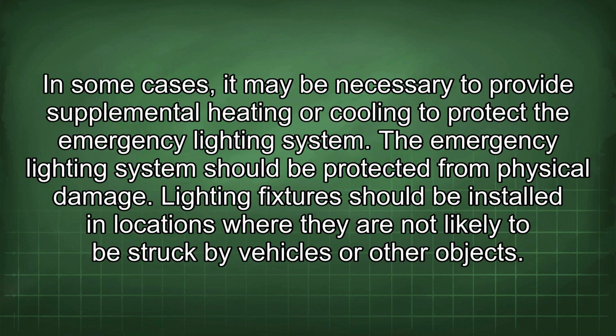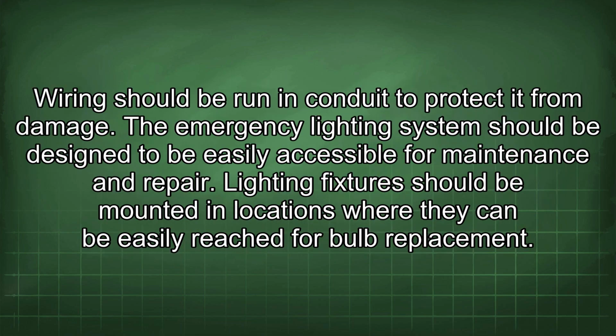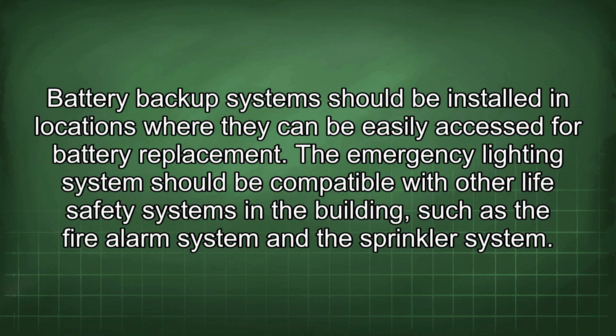The emergency lighting system should be protected from physical damage. Lighting fixtures should be installed in locations where they are not likely to be struck by vehicles or other objects. Wiring should be run in conduit to protect it from damage. The emergency lighting system should be designed to be easily accessible for maintenance and repair. Lighting fixtures should be mounted in locations where they can be easily reached for bulb replacement. Battery backup systems should be installed in locations where they can be easily accessed for battery replacement.